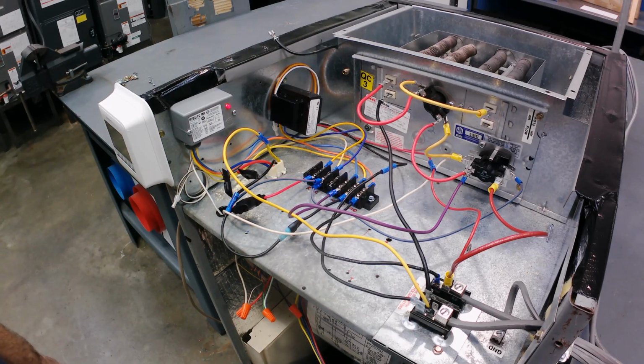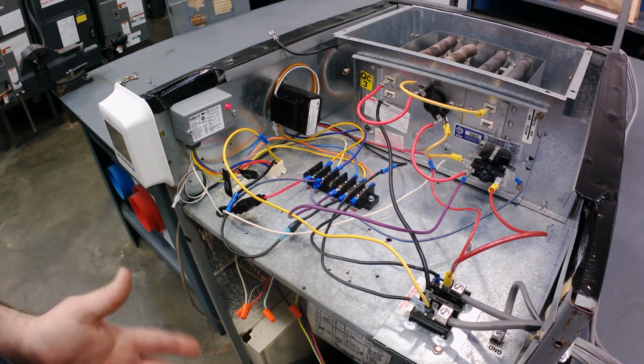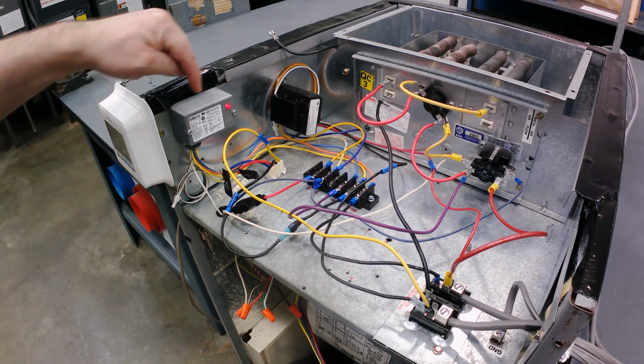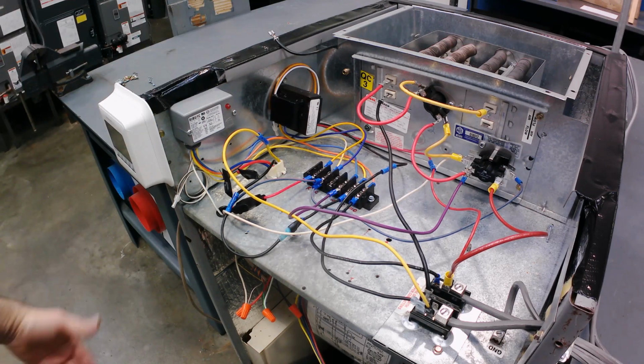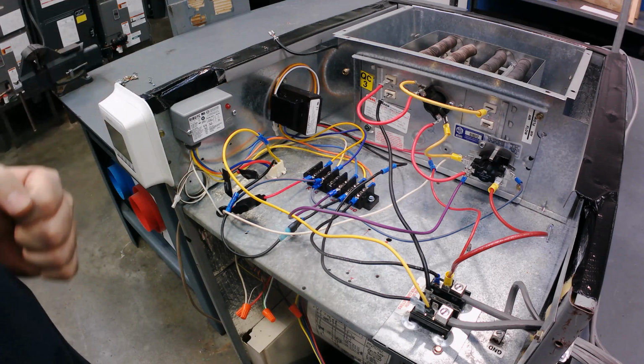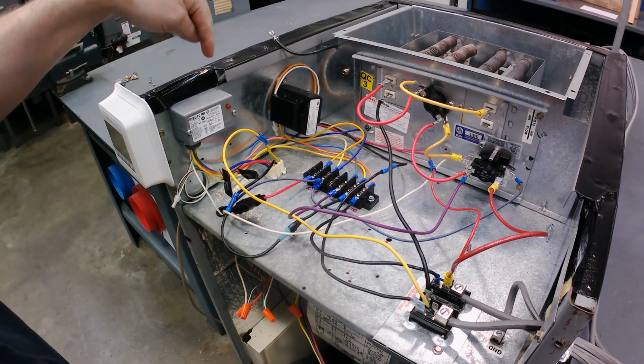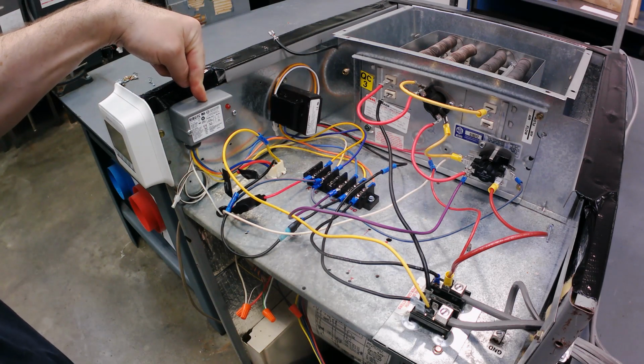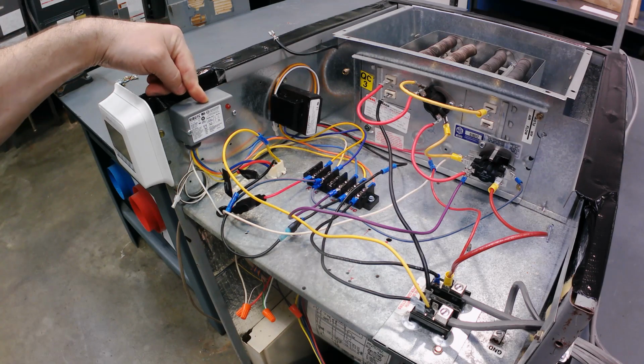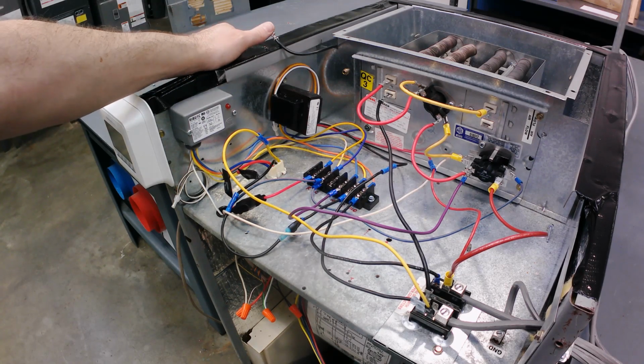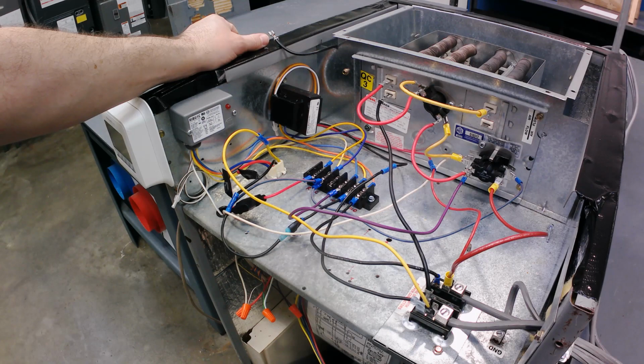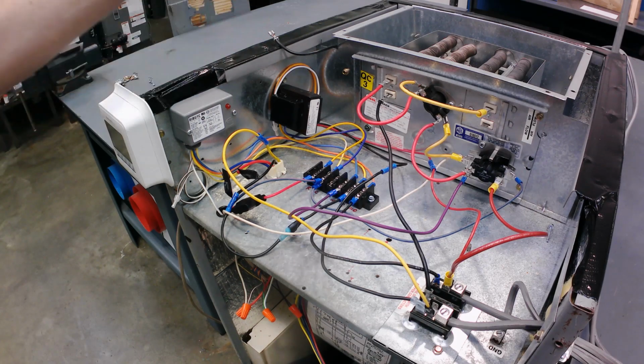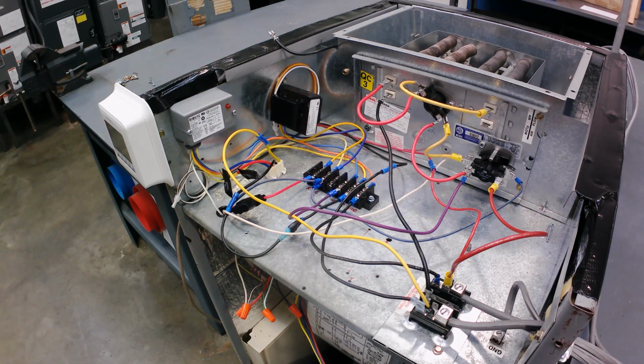that you can do, and it's half of a 9340 relay. There's only one set of contacts instead of the 9340 that has two sets of contacts. So this is a single pole double throw instead of a double pole double throw. So even though it's more used in commercial, you can still apply it using your basic thought process.